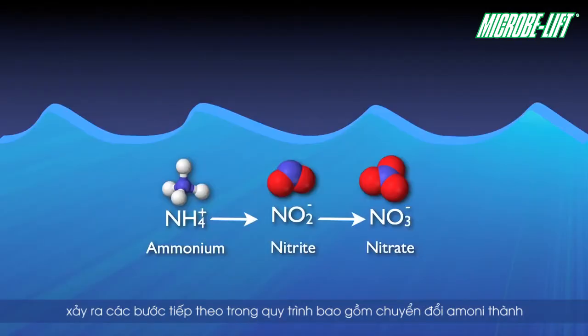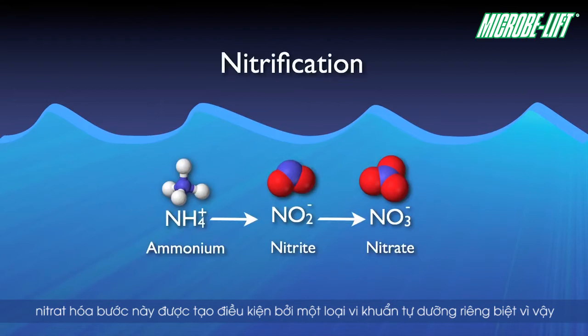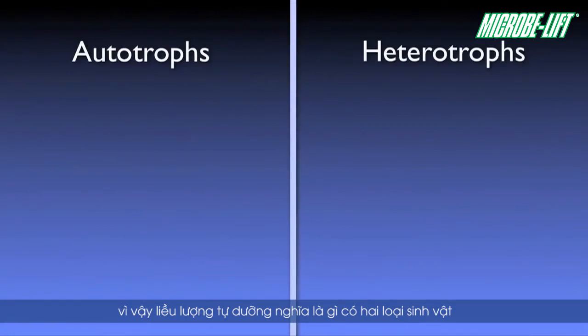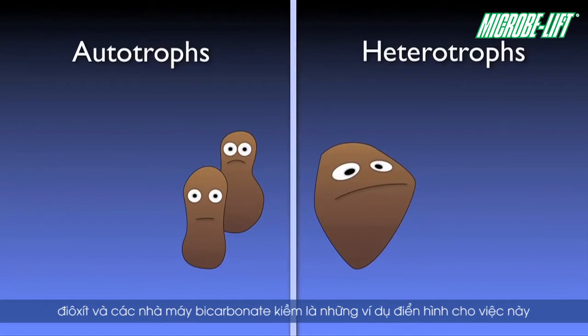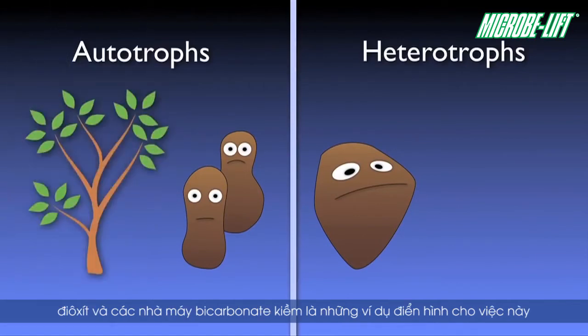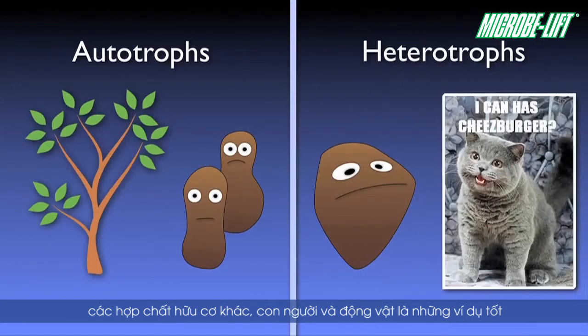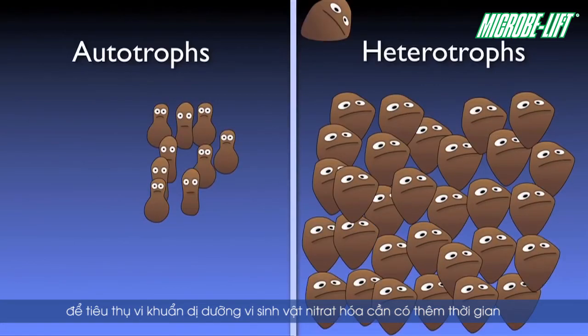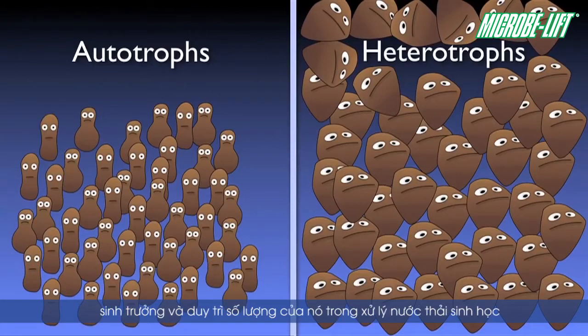The next step in the process consists of converting ammonium to nitrite and then nitrate. This two-step process is usually lumped into one term: nitrification. This step is facilitated by specialized autotrophic bacteria. Autotrophs are able to obtain their carbon from non-organic sources, such as carbon dioxide and alkaline bicarbonate — plants are good examples. Heterotrophs, on the other hand, require organic sources of carbon, essentially consuming other organic compounds — humans and animals being good examples. In contrast to heterotrophic BOD-consuming bacteria, autotrophic nitrifiers require more time to mature and maintain their population in a biological wastewater treatment system.